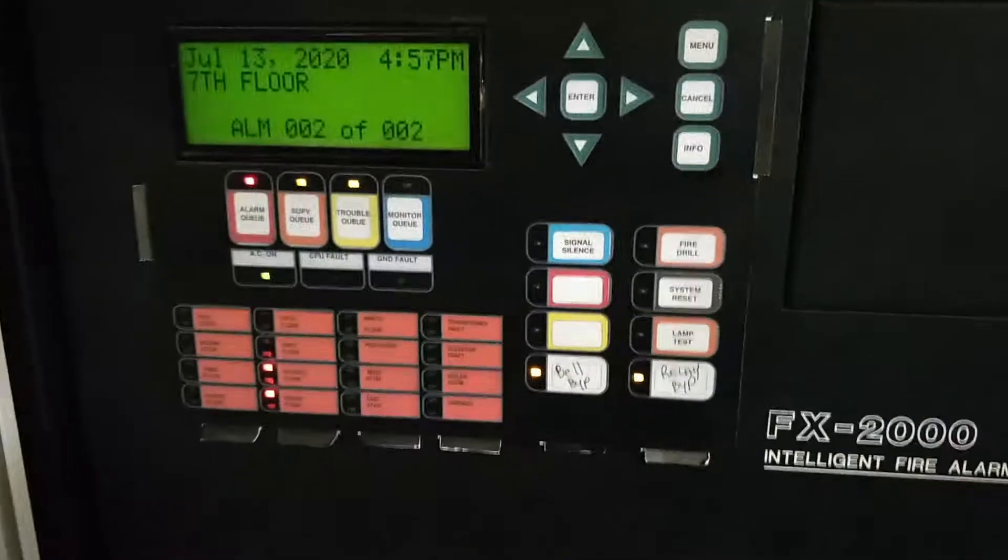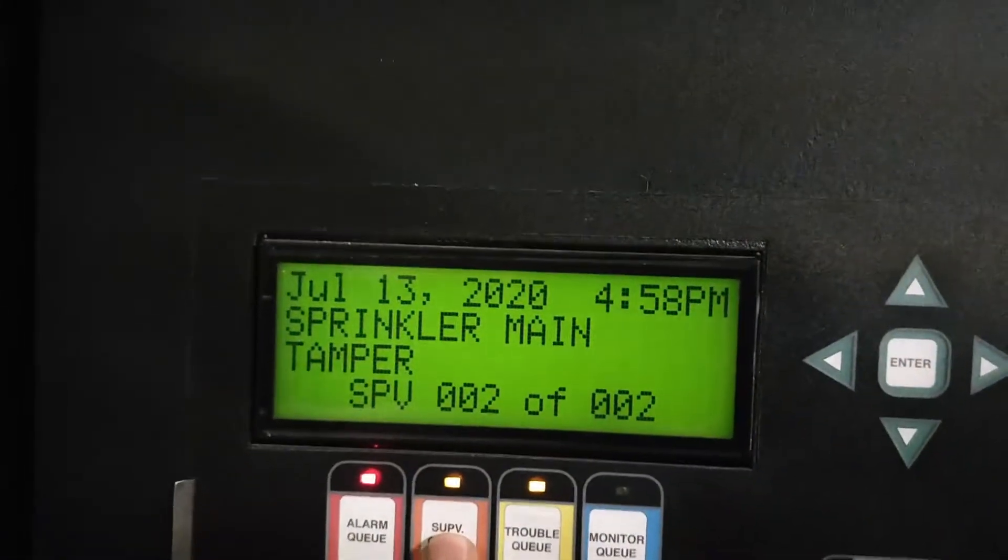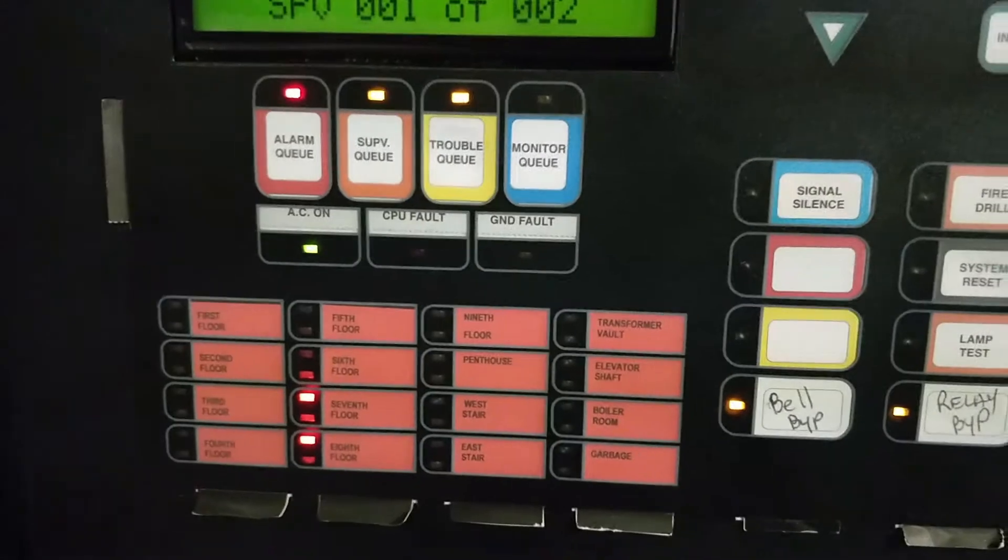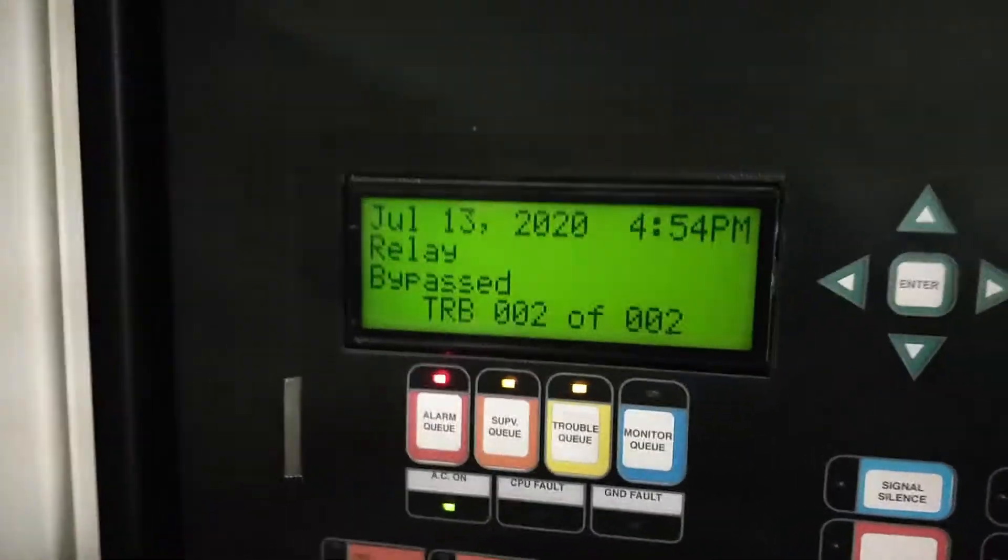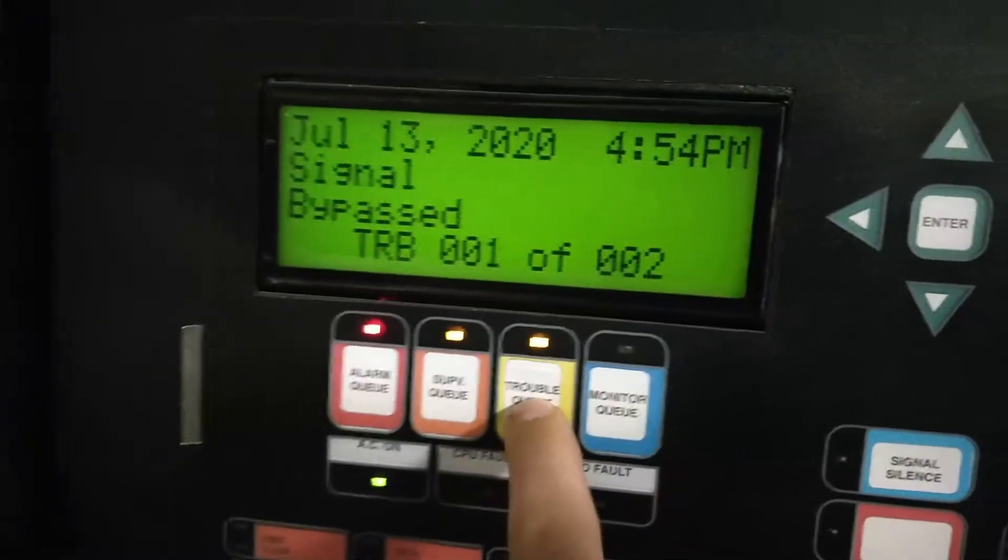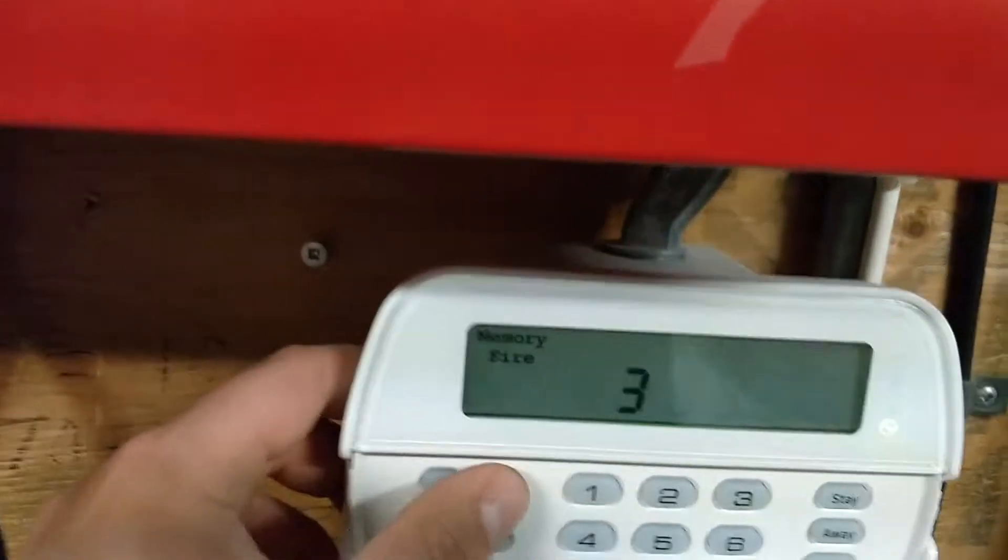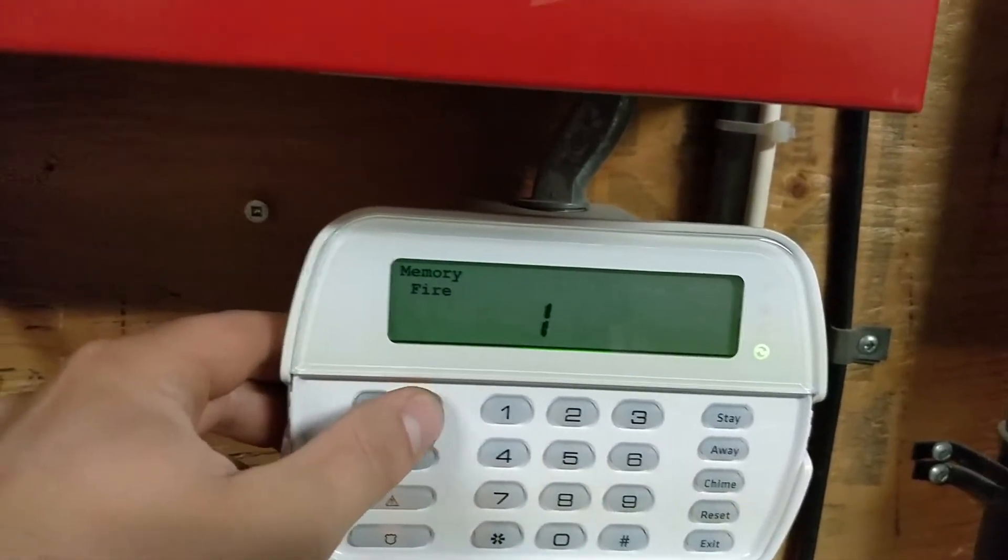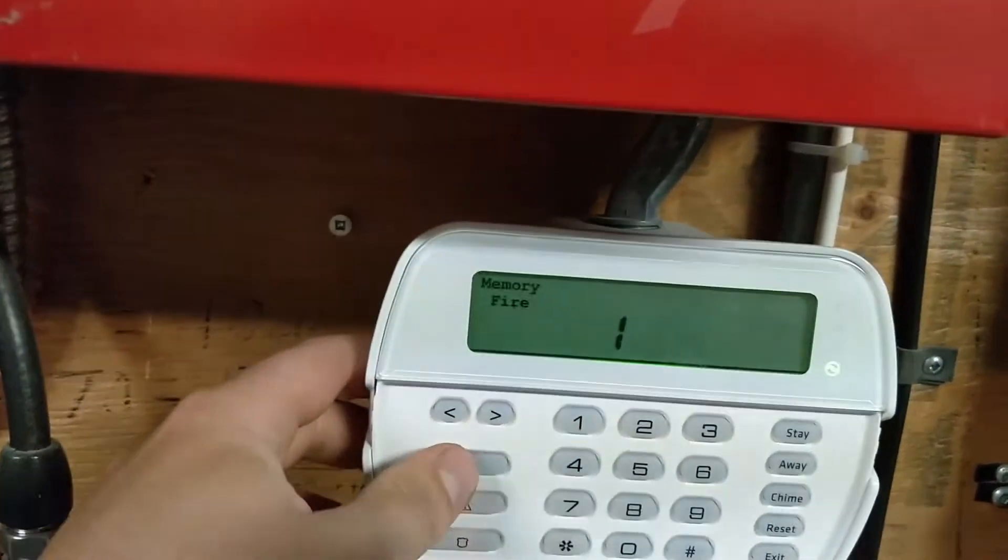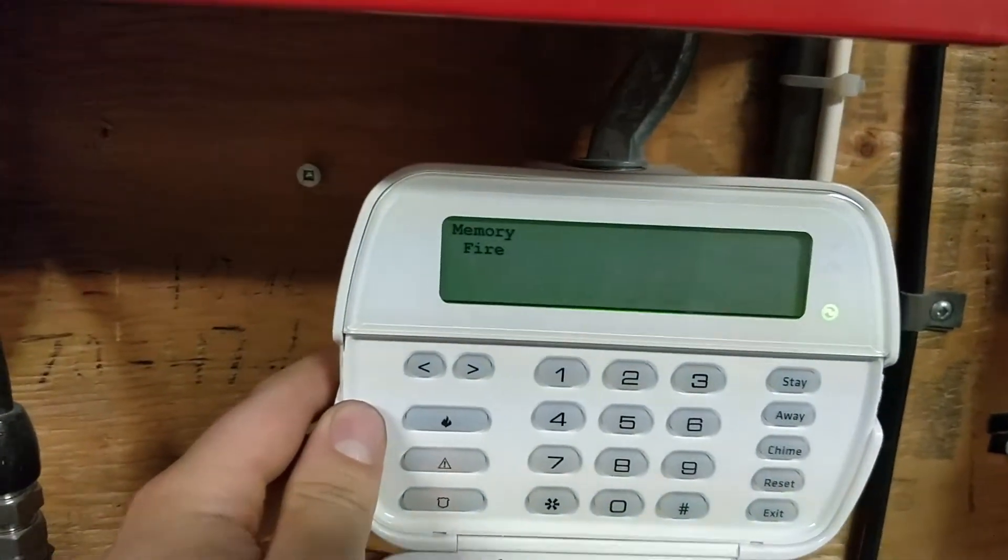Okay, so far so good. Tested a couple alarms. LEDs are matching. We did a supervisory, actually a couple of those. Those are working. There's no LED for those. Our bypasses are working. Relays - I believe there's some elevator recall here. There's I think a fan shutdown. Signal bypasses is working. We've checked our monitoring's going through. Zone 1's fire alarm. Let's see, 3 is trouble. Okay, we haven't got a supervisory yet actually, so I guess we'll take a look at that. And we gotta go look at the annunciator. Whether or not the other things are looking good.